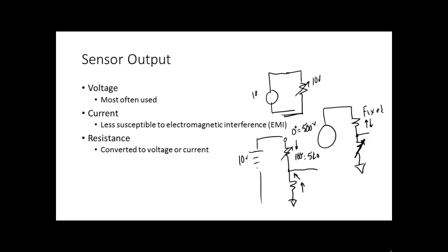You understand? So we're going to have to come up with a method where I can set the span, where I can establish what my analog input actually means. Y'all understand what I'm saying? Does that make sense? So if I get 500 millivolts out of here, and we could calculate it, but if I get 500 millivolts out there, what temperature is that? Well, if I don't set it relative to something, right? Of course, what we would do is set it relative to zero, especially centigrade. If it was a Fahrenheit scale, I would probably set it relative to 32 degrees. Or I could still set it relative to zero.